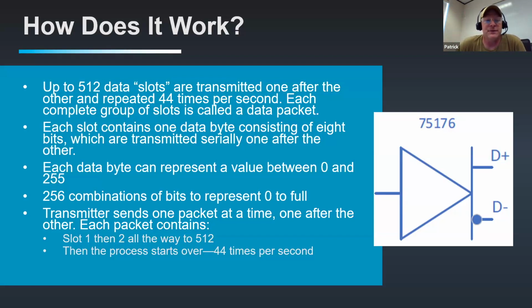Back in the dimmer days, it was way more than we ever thought we'd need. But in the multi-parameter fixture world, with an LED or a rotating gobo module or something with a fast reaction time, it can see lost packets. So it can be told in one packet to do something and not in the next. Depending on how that light is set up, it might flicker because it's trying to do all the changes, or it might not do anything, it might just sit there. So we want to make sure the integrity of our signal stays intact, because these new multi-parameter fixtures will try to do what the signal tells them, even when it's just noise and not actually being told to do something.